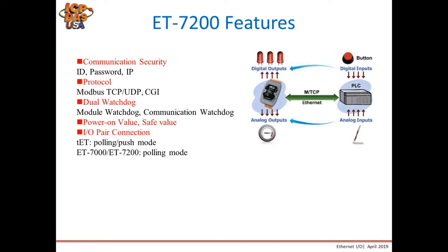Here are additional features of the ET-7200. There is ID, password, and IP address configuration for communication and security. Supported protocols are Modbus TCP, UDP, and CGI. There's a dual watchdog feature for communication and IO status. There's also a power-on value — you define the IO state when the module is powered on to avoid unwanted outputs like an open valve. And there's a safe value, so if communication is lost for too long, the module goes to a predefined safe state.